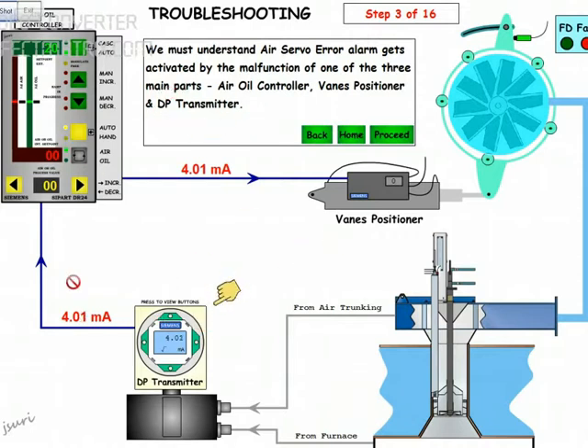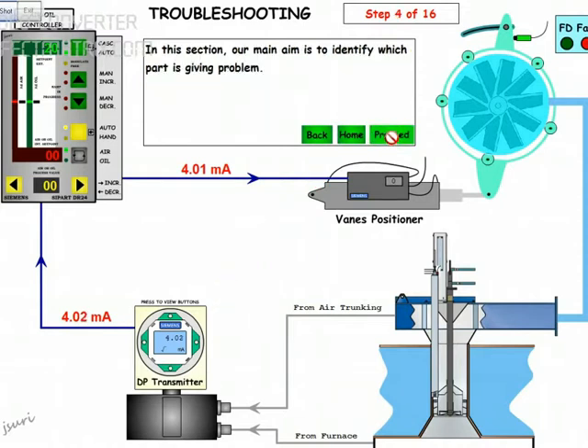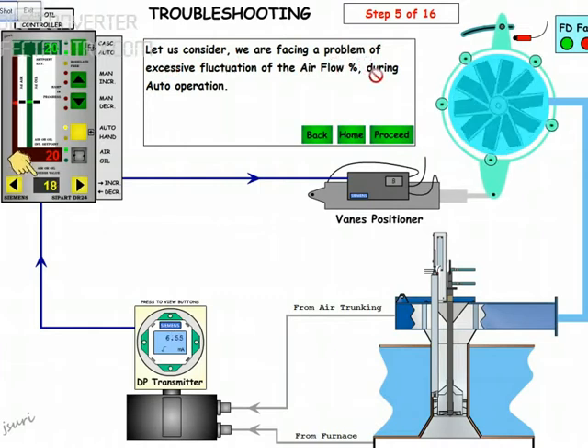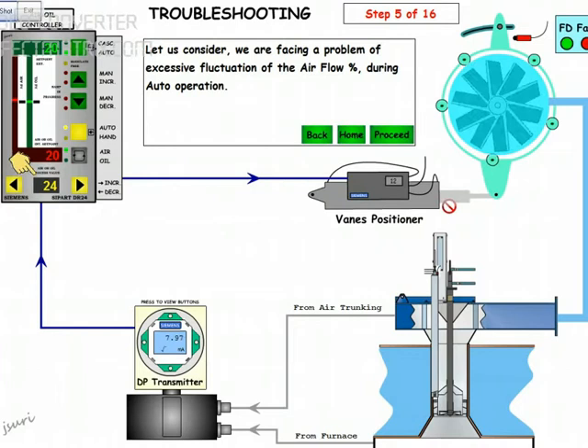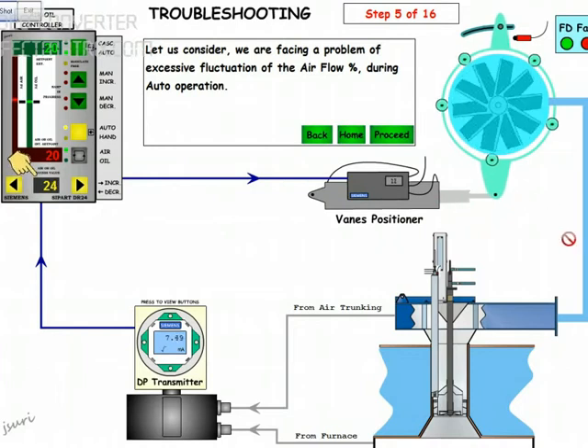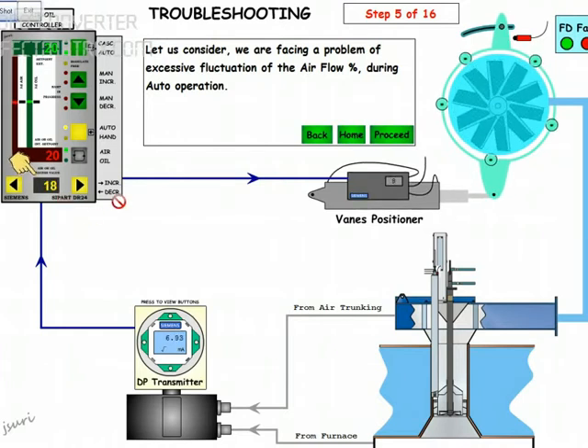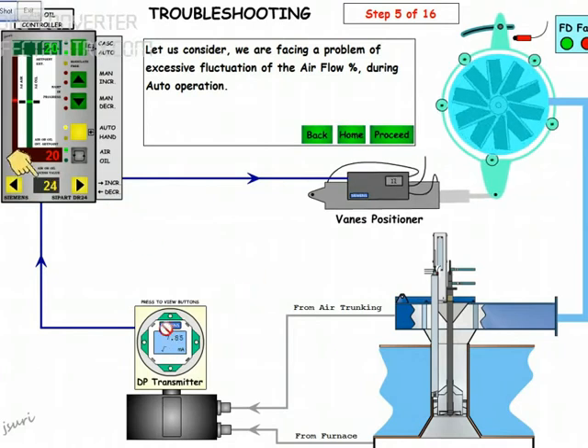Our aim is to identify which part is giving us the problem. We are facing a problem of fluctuation of air flow during auto operation. The fan is running and you can see the vane positioner fluctuating. At the same time the air oil controller is also fluctuating. All three are fluctuating and we have to identify which is the problem.